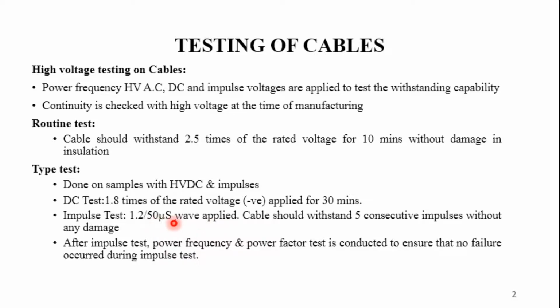As per the specification, we know that this is the general value, 1.2/50 microsecond. The cable should be capable of withstanding 5 consecutive impulse voltages without any damage. And the cable has to withstand this. Usually after the impulse test, a power frequency and power factor test is conducted to ensure that no failure occurred during the impulse test.